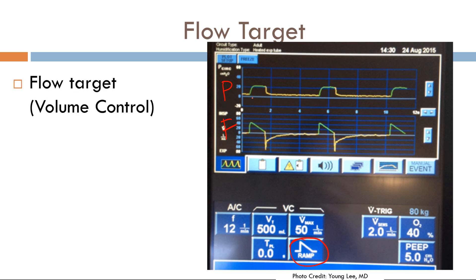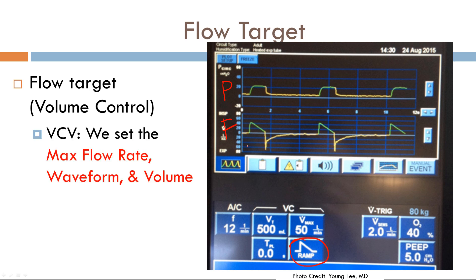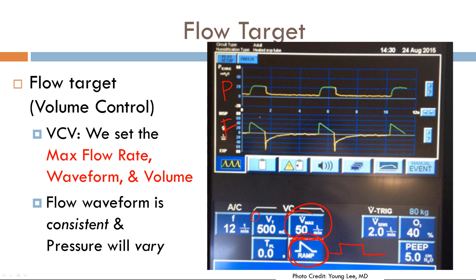Interestingly, in volume control ventilation the target variable is flow — it's kind of a misnomer; I wish it were called flow control, but it's called volume control. The target variable in volume control ventilation is flow. We set the maximum flow rate, here set to 50, and what the waveform should look like — for example, a decelerating ramp. In flow-targeted modes such as volume control ventilation, you set the flow rate as well as the waveform. You also set a volume, which I'll discuss later. The flow waveform is consistent as the independent variable, while pressure varies as the dependent variable.